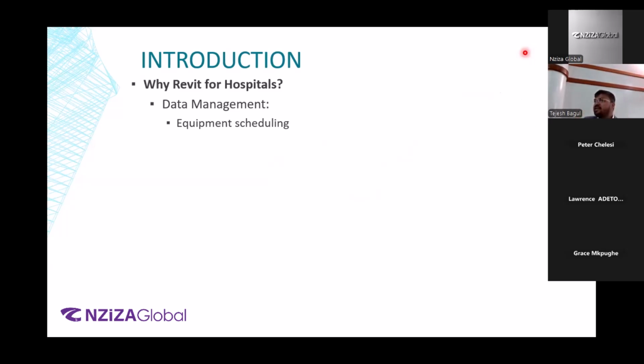Revit, specifically Revit, will help you properly put that information together in the equipment schedule, whatever you call it. All right. Under that, let's say you have a big air handler and you have different parts. It's a custom air handler. You have ordered the fins from a vendor. You've ordered a fan from another vendor. You've ordered, let's say, an airflow monitoring station from another vendor. So properly scheduling those parts can also happen in Revit itself. You do not need to go into another app or another application like Excel or AutoCAD to make it happen. It can happen in Revit only.